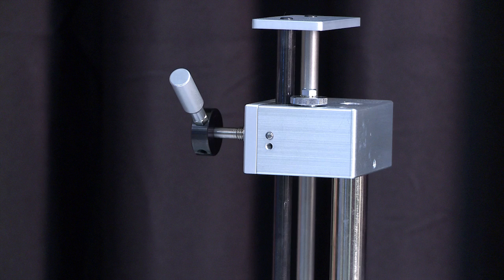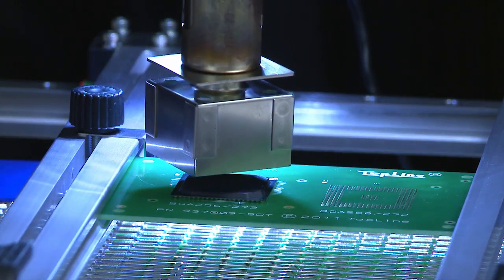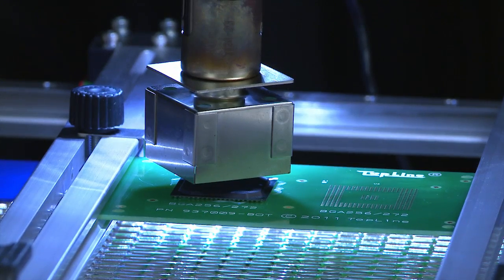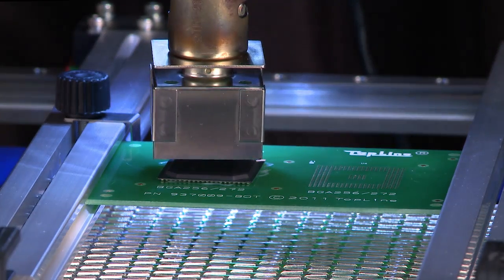With the lock lever at the top of the handpiece fixture tower, lower the head down over the component to adjust the theta. Be careful not to touch or nudge the component or board as this will knock the alignment off.